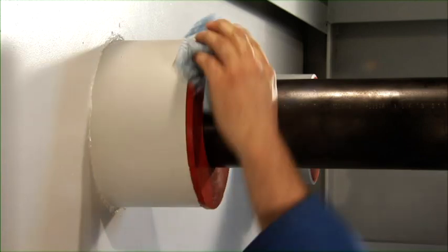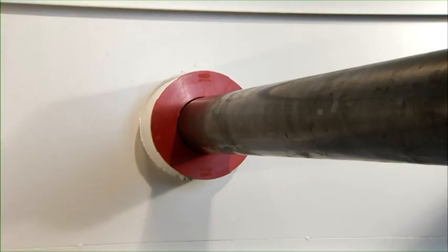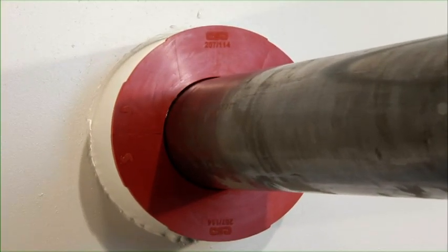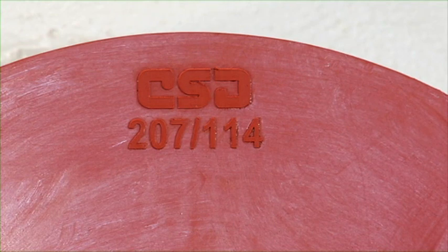To ensure optimum tightness, the proper selection of the plug has to be based on the inner diameter of the conduit sleeve and the outer diameter of the ducted pipe. The plug size is visible on the flange of the plug.